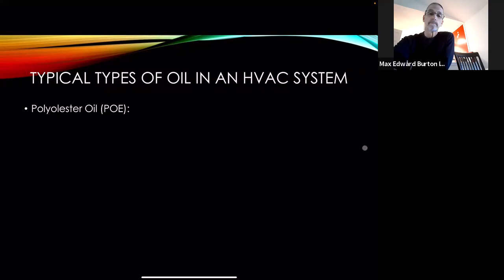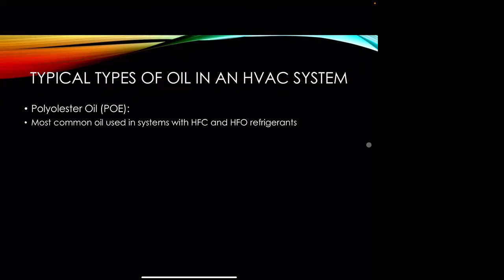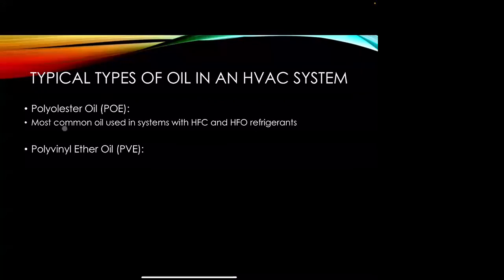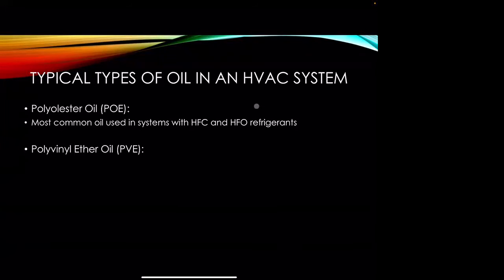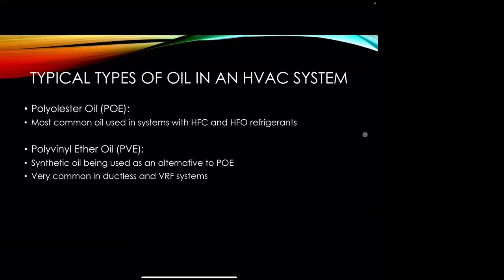R410A. It's the most common oil used in systems, again, with the HFC and HFO refrigerants. And then we have PVE oil, or polyvinyl ether oil. This is a synthetic oil that's being used as an alternative to POE oil. It's very, very common currently in ductless systems and VRF systems.